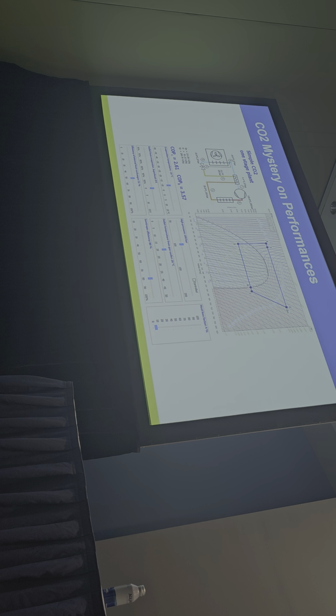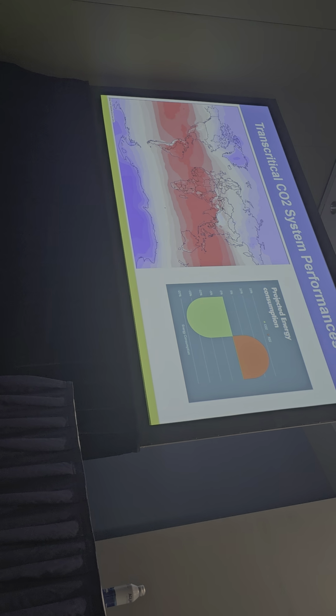Colder it's going to be, I'm going to get left, left, left, and left. And when I'm moving left with that vertical line, I'm creating less flash gas. If I'm creating less flash gas, I'm more efficient. If I'm more efficient, my COP is going up. This is what happened with a CO2 system. And again, it took me quite a long period of time to really understand the entire dynamic of this.